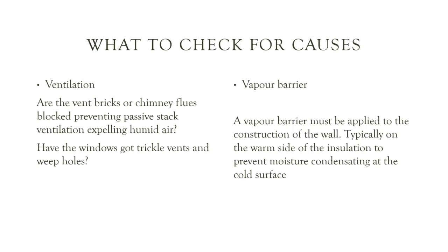Ventilation. So we spoke about this before. Are the vent bricks or chimney flues blocked? Are the vent bricks even there? This prevents passive stack ventilation expelling humid air. Refer to the first slide where we looked at the passive ventilation, about the cold air coming in, fresh air coming at the bottom, and expelling the warm, humid, stale air at the top. The vent bricks in the chimney flues, they have a role to play with that. And so are the windows with their trickle vents and the weep holes to get rid of condensation and to vent out air.